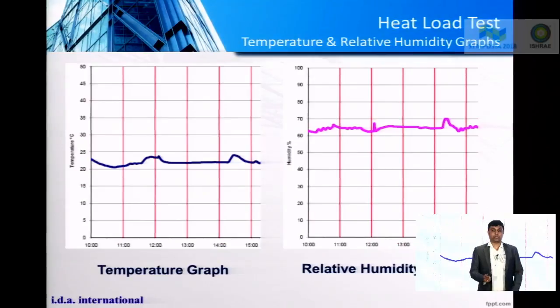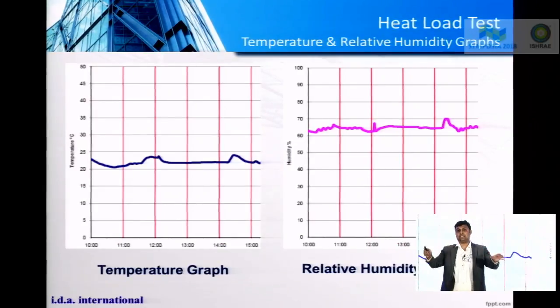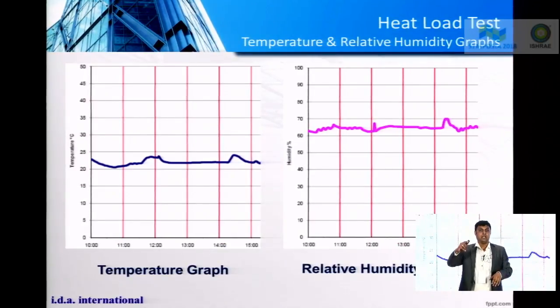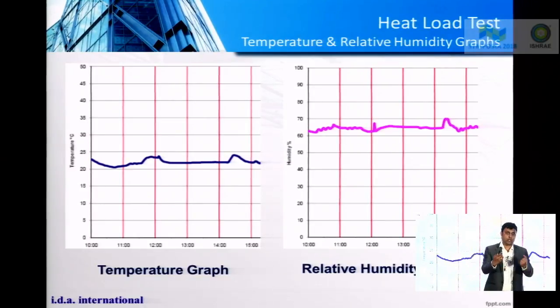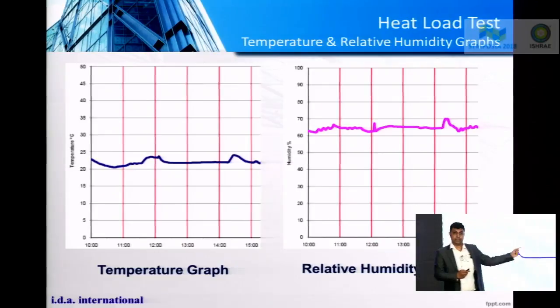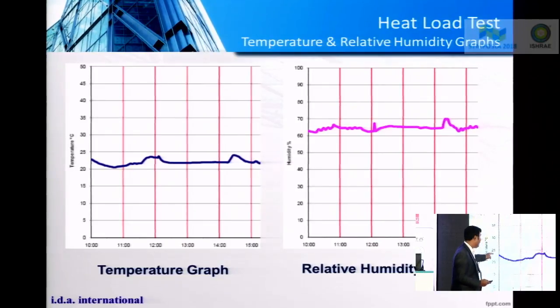Once you do a heat load test, you have different sensors, right? You have temperature sensors and humidity sensors across the cold aisles and hot aisles. I will collect all the data. It's important to collect the data and create graphs.